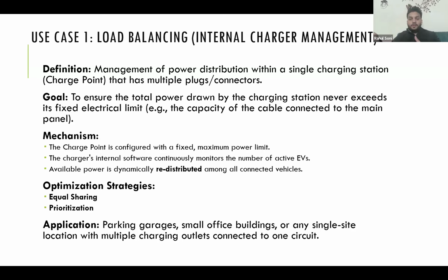Second way: all the cars are plugged in, like 50 cars charging at the same time, so you're dividing each charger at 2 kilowatts. Another strategy: suppose you're there for an hour or half an hour, so you dedicate 2 to 3 or 4 chargers with a maximum power limit, like 10 kilowatts for 3 chargers — 30 kilowatts allocated to just those 3 — and the rest of the chargers are allotted equally or based on priority.